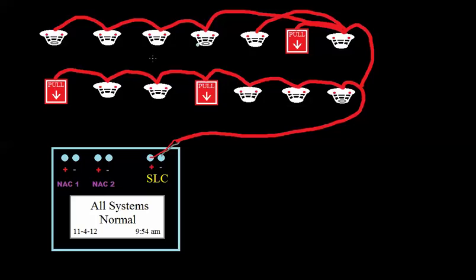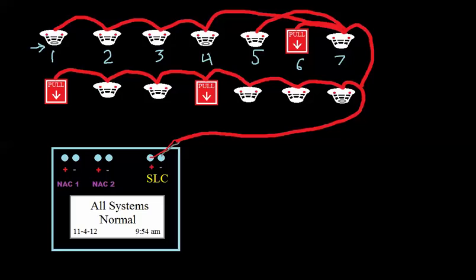So the way this works is, when I install new devices, I have to go into the panel and program these devices, and I have to tell the panel that these devices exist. So let's label these devices. Let's say that this heat detector, and I can tell it's a heat detector because you can see that little gray ring at the bottom. That indicates that it's a heat detector. Let's call that device one. Then the smoke detector is two. Next smoke detector is three. Heat detector four. Five. This is a pull station, six, seven, et cetera. And then start over on the bottom. We go eight, nine, ten, et cetera.